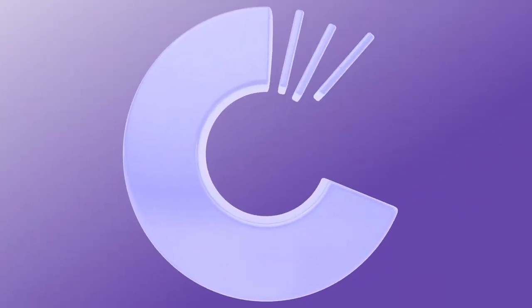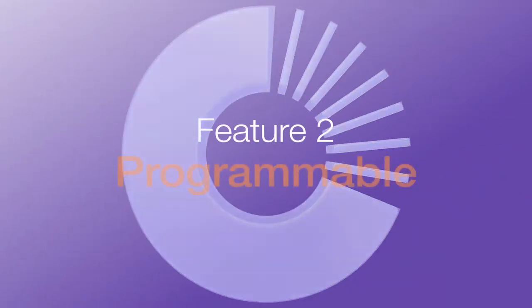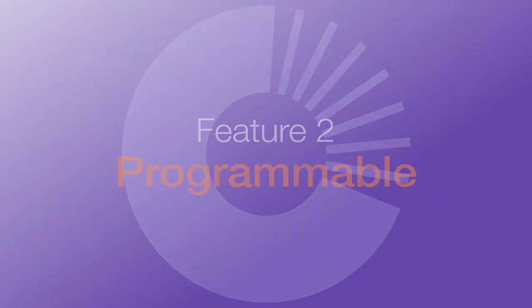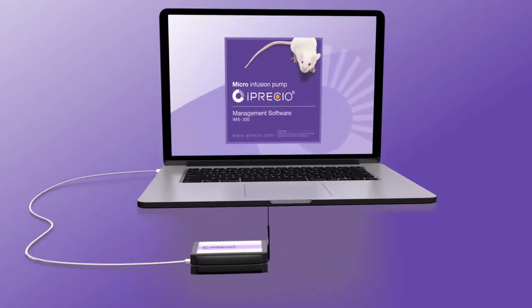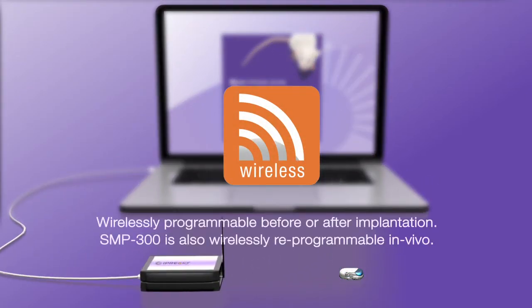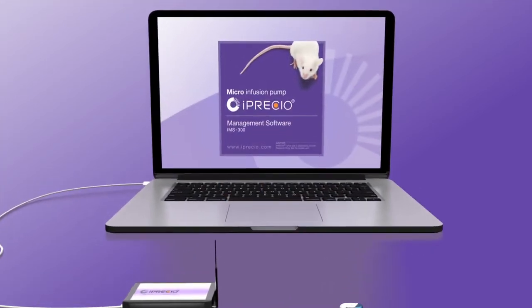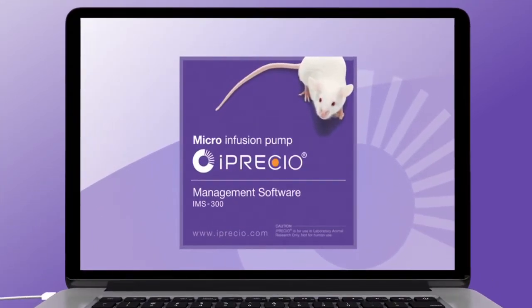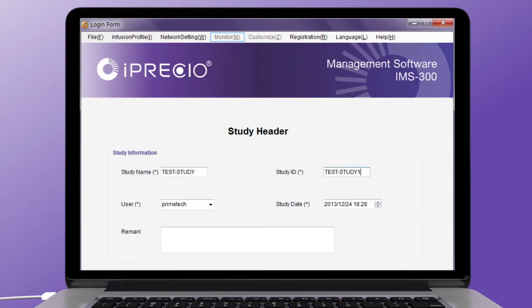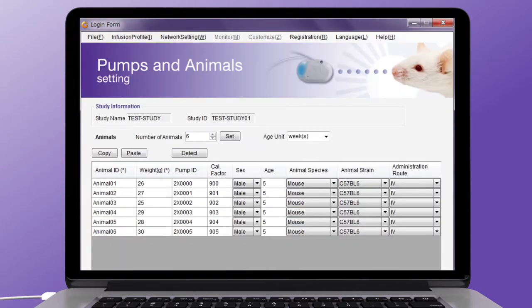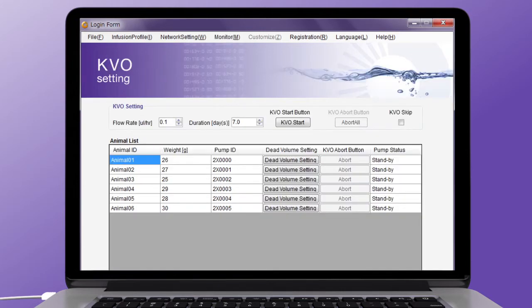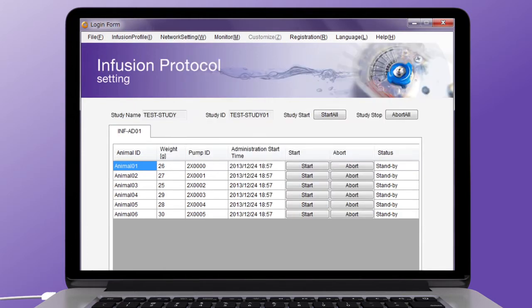I will now discuss the second key feature of the iPrecio pump: pre-programmable. Programming of the iPrecio is accomplished through a wireless communication device connected via an Ethernet cable to a PC using Windows-based management software. Using the menu-driven software, header information along with infusion protocol details are entered and ultimately downloaded to the pump's flash memory.